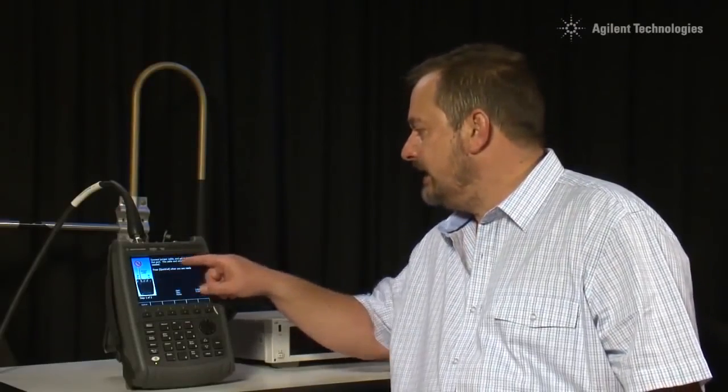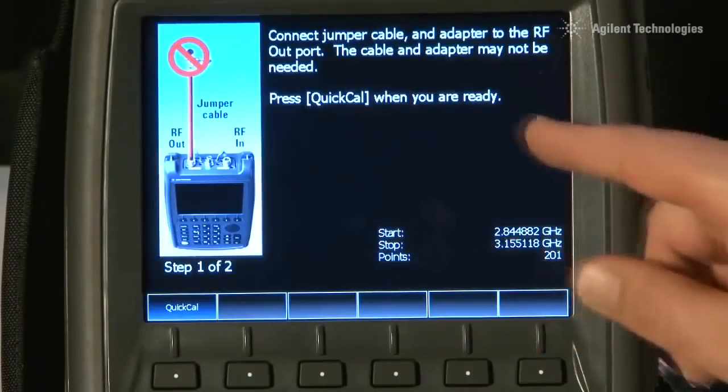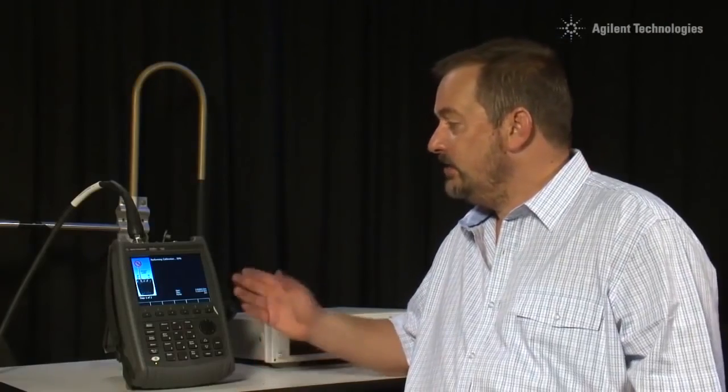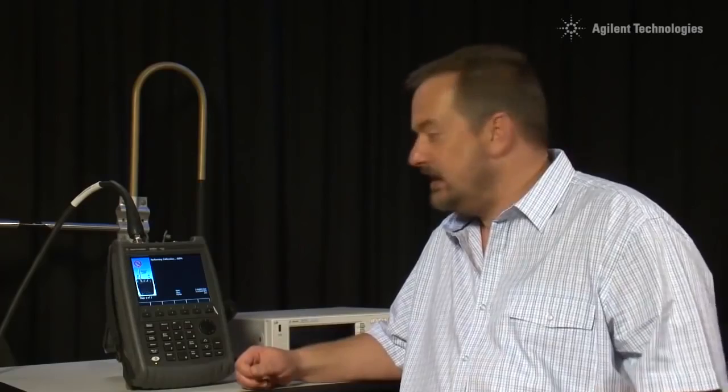and adapter to the RF out port. The cable and adapter may not be needed, but we want to calibrate out the effect of this cable. It says, Press QuickCal when you are ready. So I will press that, and it is now performing the calibration. It is just using the open circuit end of the cable. It does not require any specific standards.